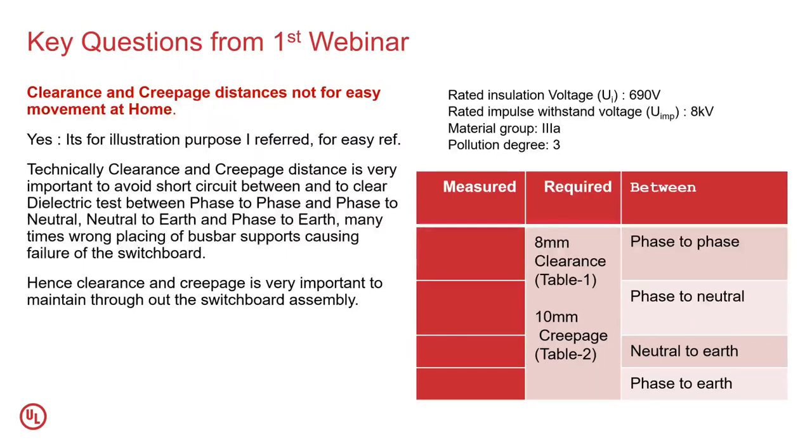It was to keep the characters in our mind so that we can follow the standard easily. Throughout my presentations, I try to link the technical points of the standard to our regular daily life so that you will remember those key points. Technically, clearance and creepage distances are very important to avoid short circuit between phase to phase, phase to neutral, and phase to ground, and also to ensure that the dielectric HV test is cleared during testing. They are very important to maintain within the switchboard to ensure there is no short circuit or dielectric failure.